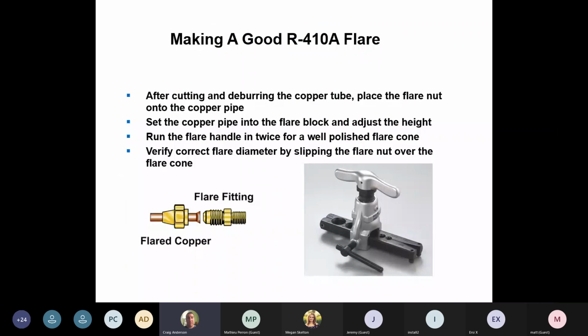So, making a good 410A flare, what we talked about before: a good flaring tool. Make sure that our cutters did a great cut, we've deburred the copper, and no filings are in. Get your flare nut on there, get your flaring tool, and make a nice flare. We don't want any sealant on that flare. Sealant, if it gets into the system, could make a mess. It gets hard like bubble gum and gets stuck to the side of the refrigeration line. It's restricting the flow of the Freon going through the line, especially when we're in modulation on these compressors and EE valves. Little restrictions make a lot of headache for the service guy that's going to the next. So make sure you've got a good flare, you've deburred it, and you're ready to go.